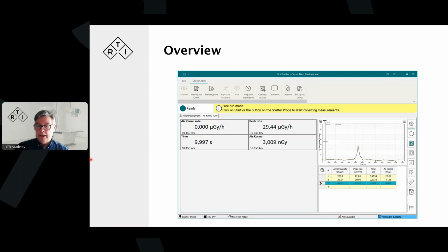And of course, changes in the background radiation, you won't really pick that up if you're doing a survey, which is for one exposure, because you start the measurement, make your exposure, maybe 1 second or 5 seconds maximum, and then you capture data. That's maybe a total of 10 seconds. Then the variations in the background radiation would not be that big.